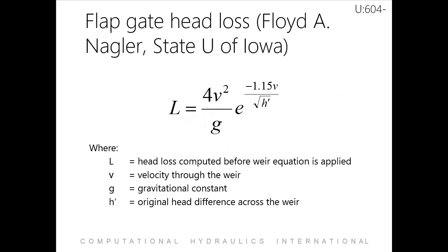As mentioned earlier, there are head losses associated with flap gates. Often weirs, or orifices, are installed with a tide gate at points of overflow into receiving waters. Flow across the weir is restricted by the tide gate, which may be partially closed at times. This is accounted for by reducing the effective driving head across the weir according to an empirical factor, where h is the previously computed head before the correction for flap gate, and v is the velocity of flow in the upstream conduit.